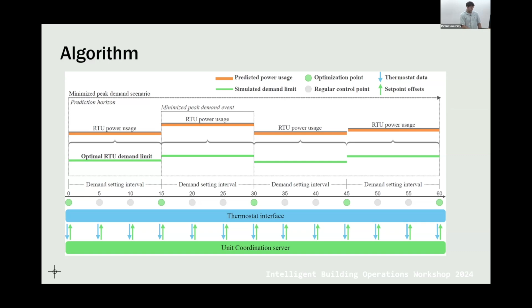It was important to make a distinction between the unit coordination server and the thermostat interface, because the interface is going to change. You're going to have a JACE, or you're going to have an Ecobee thermostat, or some sort of smart thermostat. And so you need to design a control layer that is agnostic to the unit coordination algorithm. The unit coordination algorithm should just receive the variables that are needed to run the optimization, and it should not care at all what it's interfacing with on the other side. So there should be an interpreter layer.